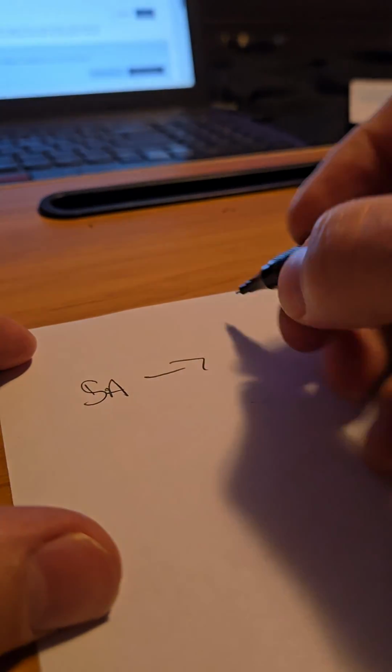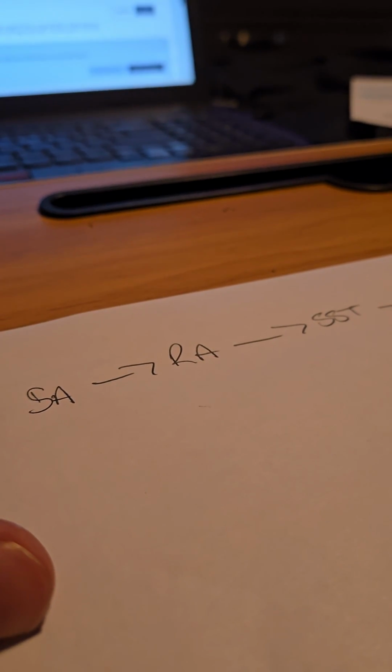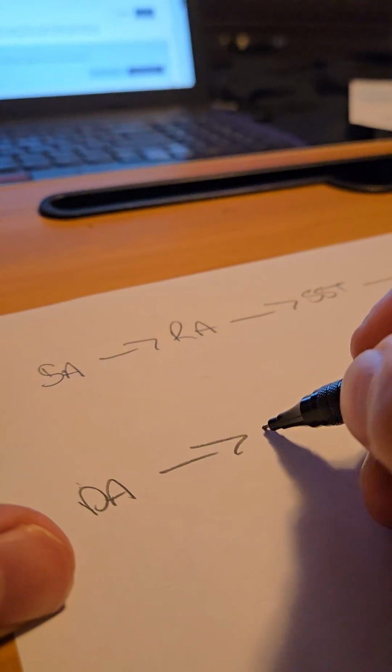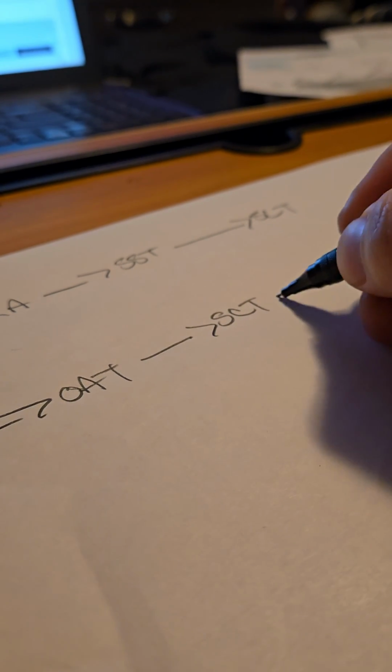This one's for Ahmed: design conditions, which I need in order to explain question 9. If you don't know this, you really should. So before any test, I write this down. It goes supply air, 2, return air, 2, saturated suction temperature, 2, suction line temp, 2, discharge air, 2, outside ambient temp, 2, saturated condensing temperature, 2, liquid line temp.